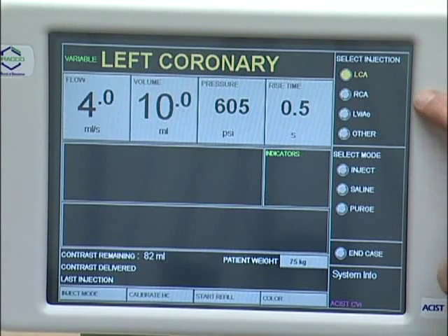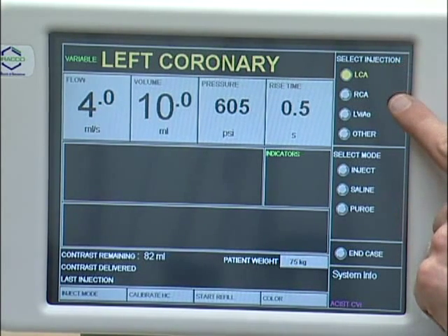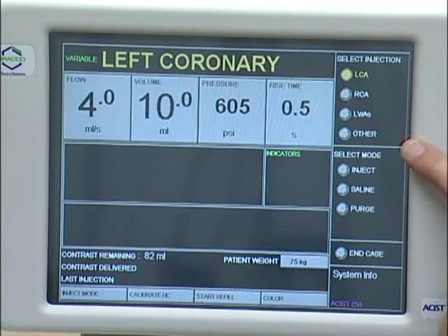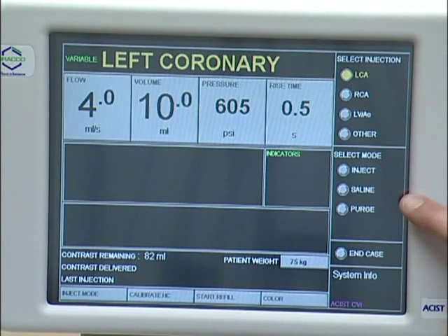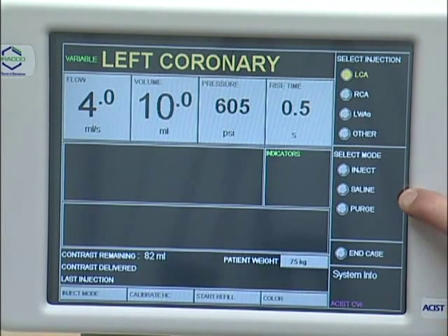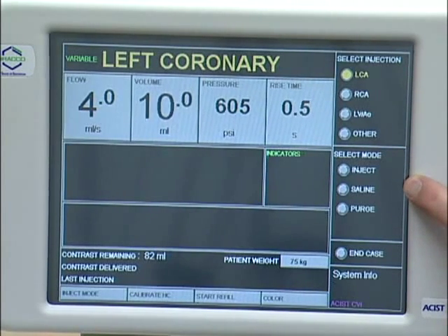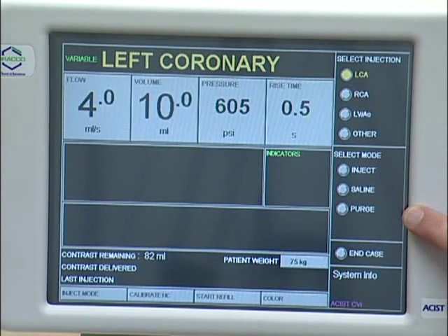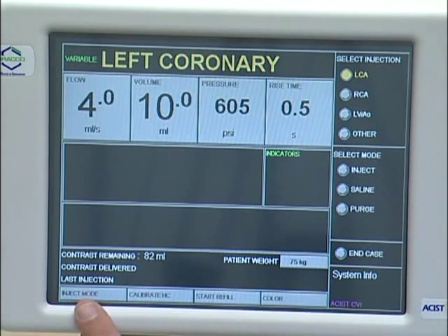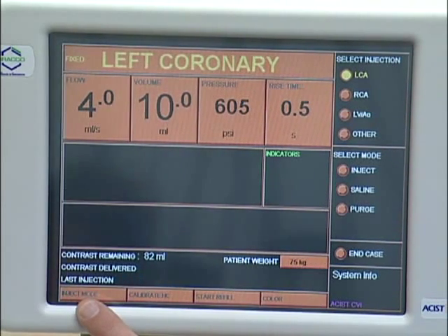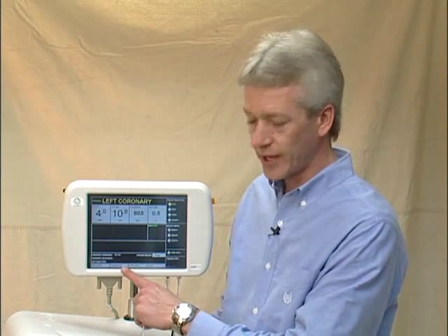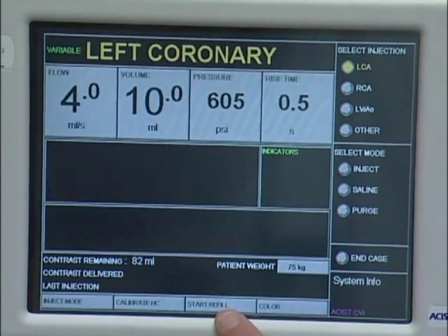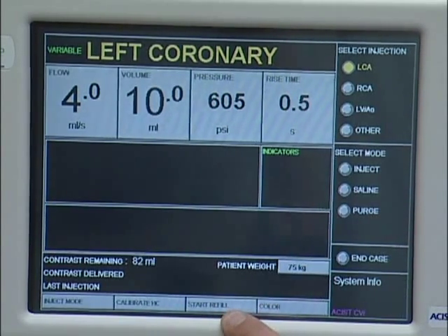On the right side of the screen we have the types of injections that we do, which is the left coronary, the right coronary, the LVAO, and an other. Following down the right side we have the three different functions that the system can do, which is inject contrast, flush with saline, or purge contrast. Continuing on to the bottom of the screen we have the mode button, which as you see on the top we're in the variable mode. If I touch the mode button I turn into a fixed mode. The hand controller calibration is initiated from the center button. Continuing on we have the start refill button. The start refill will start and stop the refill, and also has an automatic refill function as well.